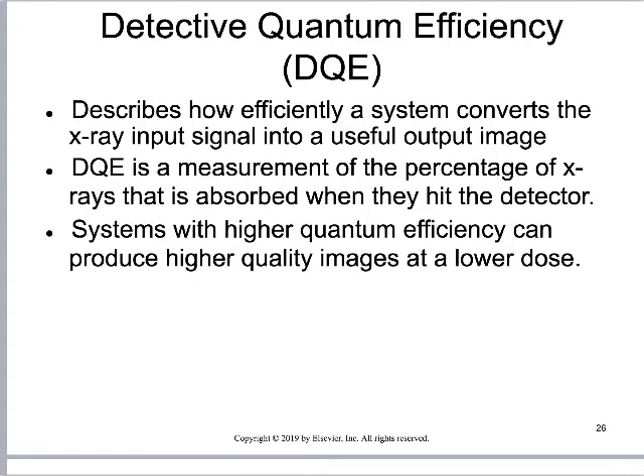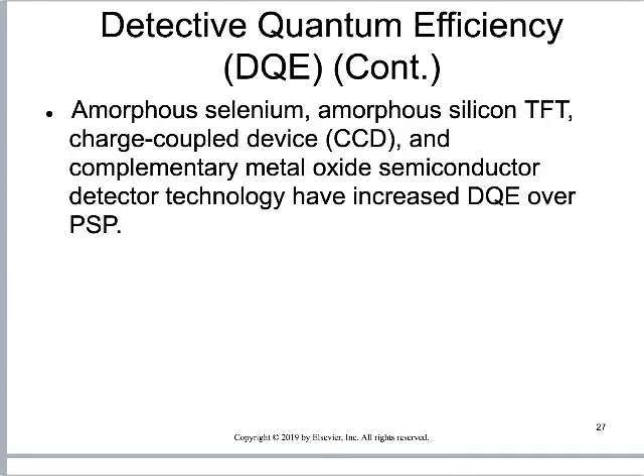Ways to improve exposure latitude include increasing bit depth, but they also involve the actual hardware used to acquire images. Detective quantum efficiency (DQE) refers to how efficient the image receptor is at taking an x-ray photon and turning it into a signal the computer can process. DQE is a measurement of the percentage of x-rays absorbed when they hit the detector. A system with higher DQE can produce a higher quality image at a lower patient dose. This is one major reason we've moved from photostimulable phosphor technology to flat plate technology — flat plate has a higher DQE. Amorphous selenium, amorphous silicon, thin film transistors, and charge-coupled devices all have an increased DQE over photostimulable phosphor systems.